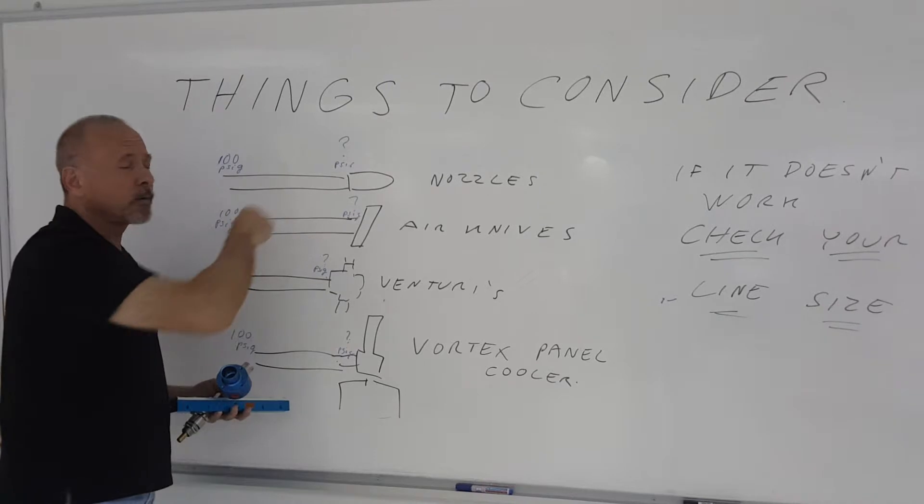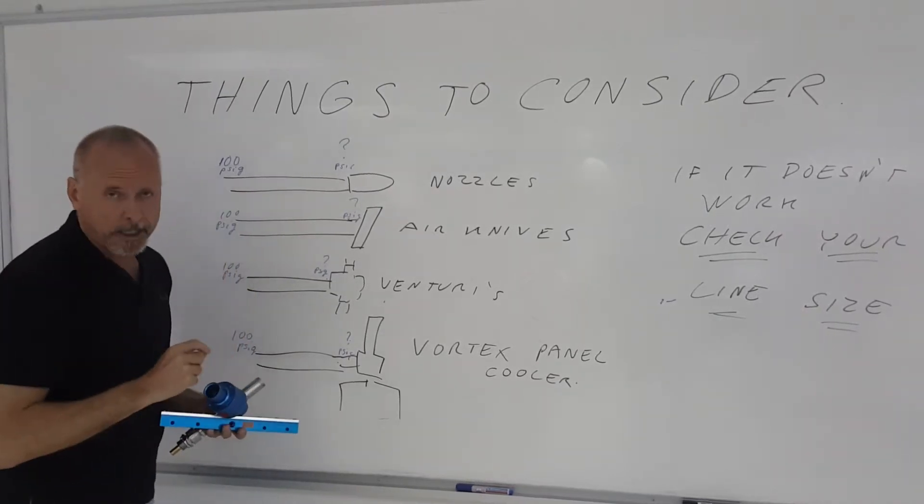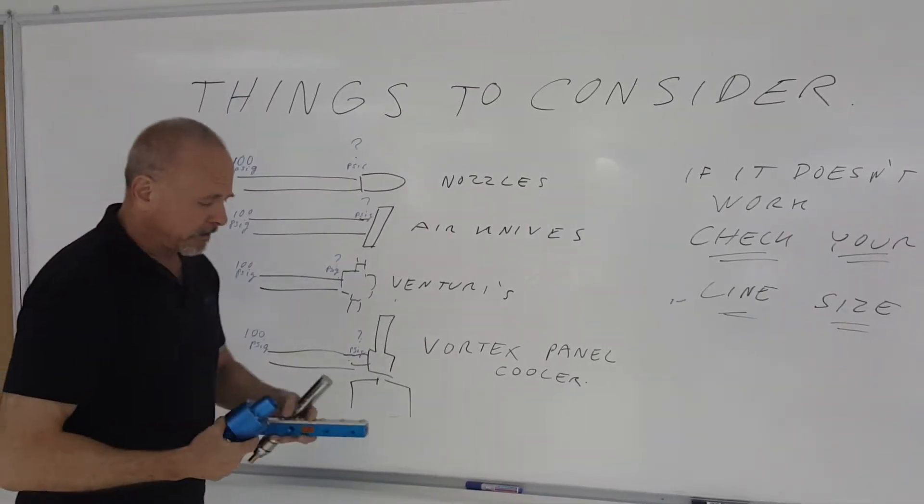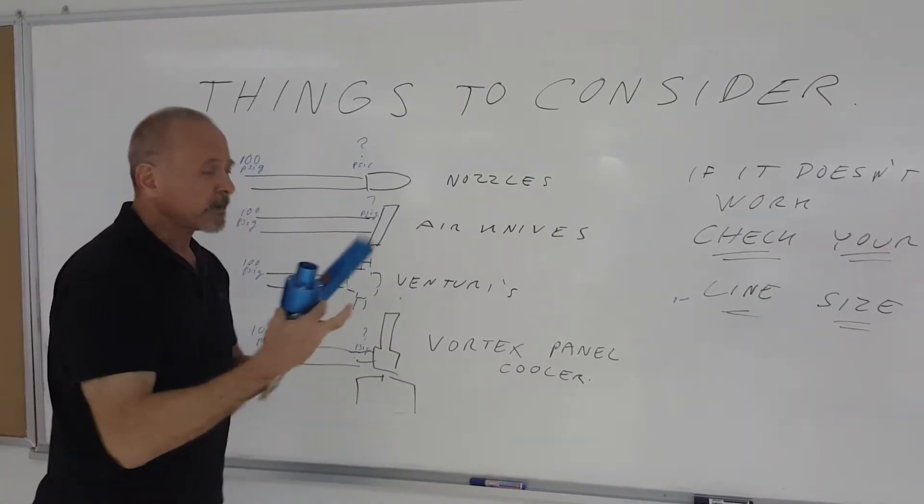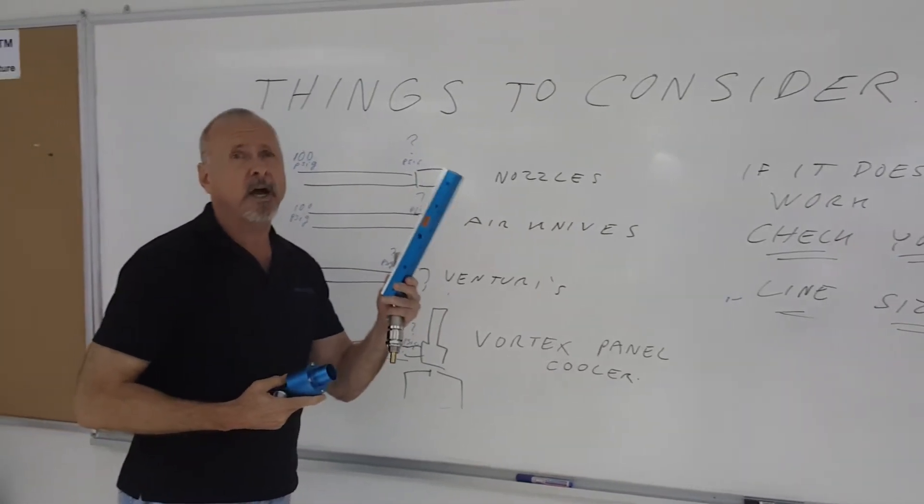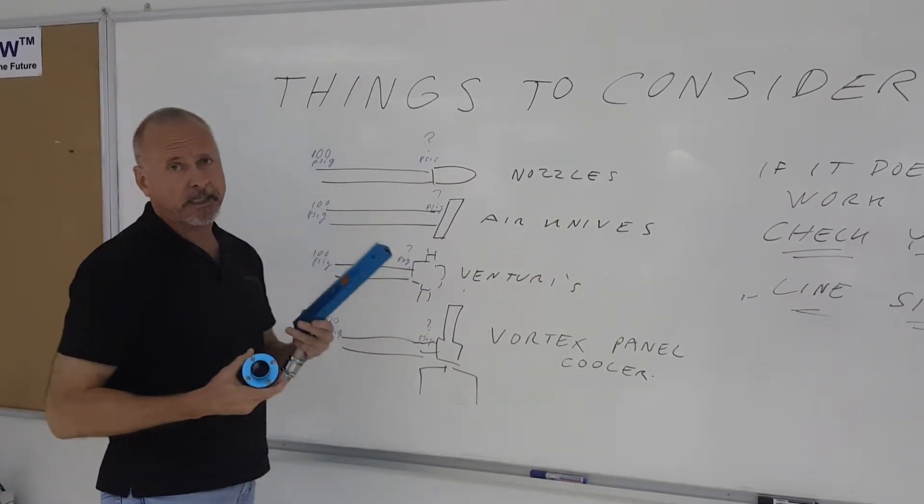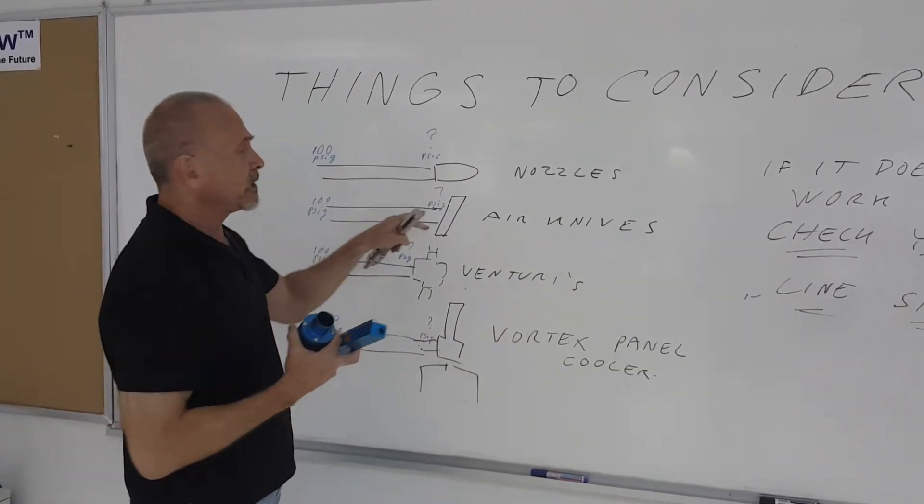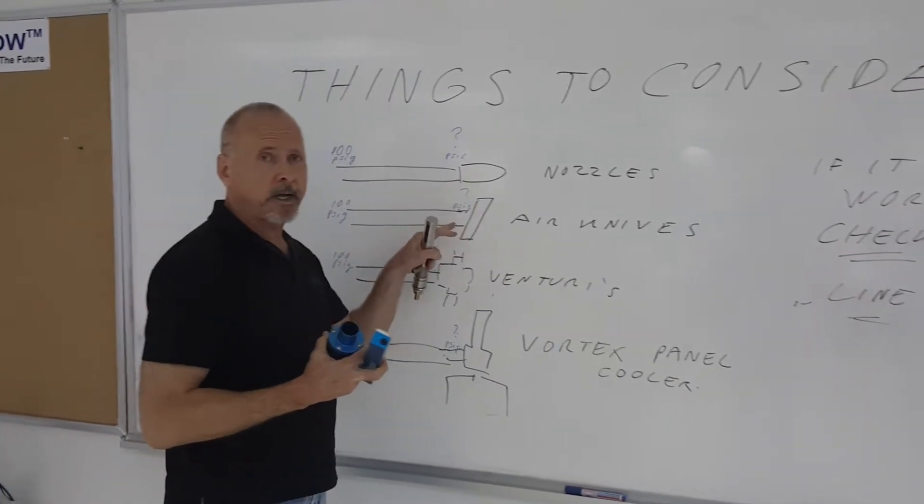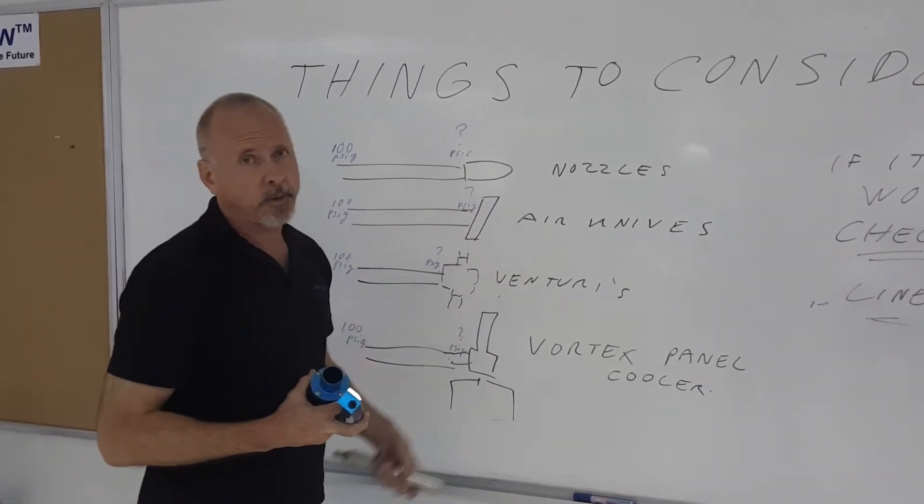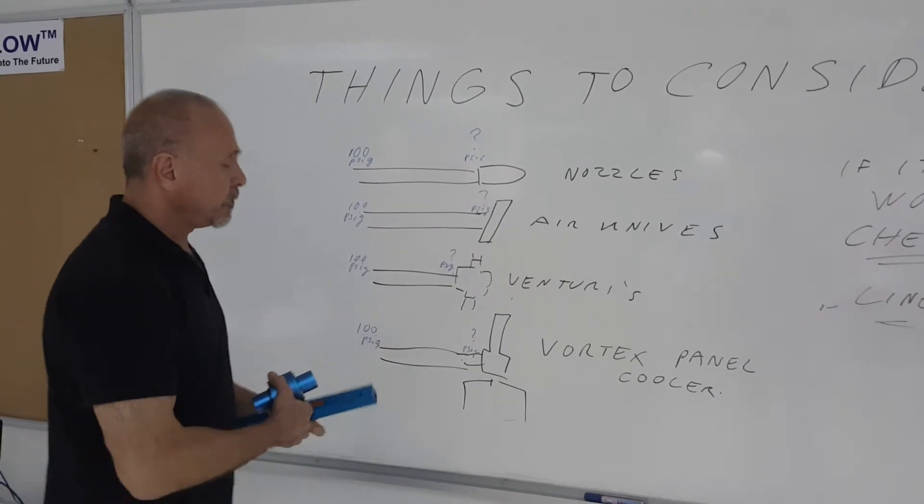Similarly with air knives - I have an air knife here in my hand. An air knife is going to use more air than a nozzle typically, so you have to be a bit more careful on the size of that supply line. Again, you'll have a pressure drop as it goes through that supply. If the line is too small, you're going to have a problem.